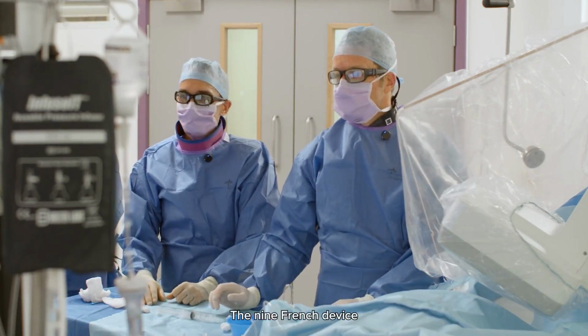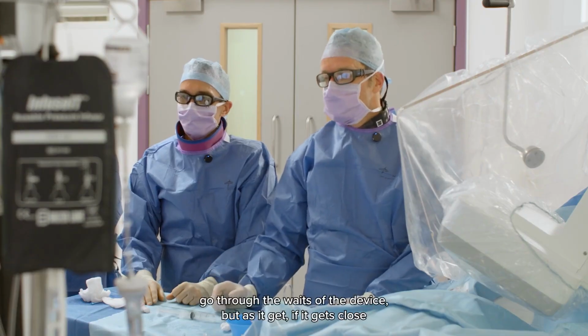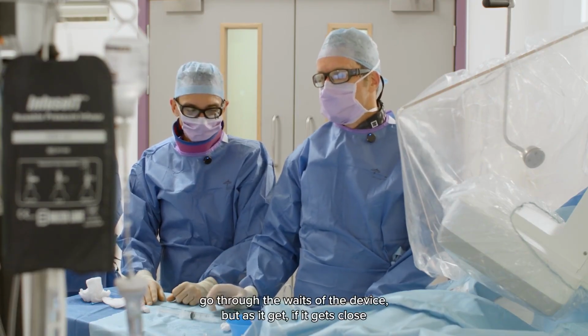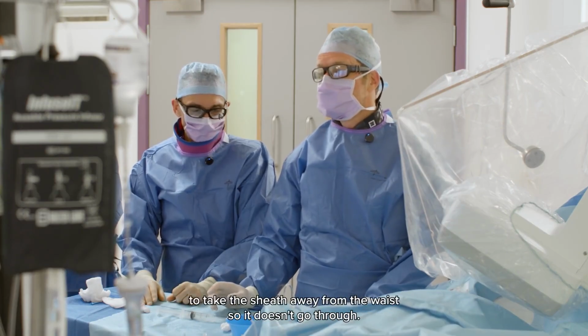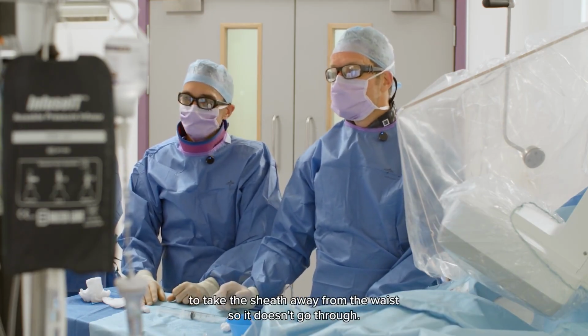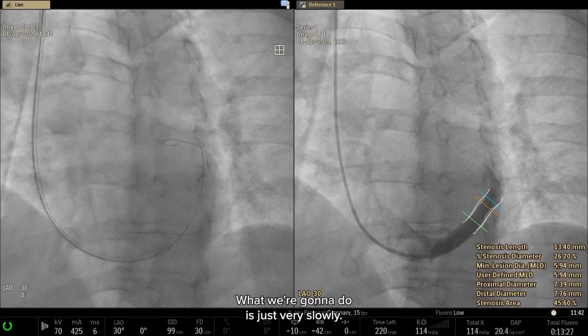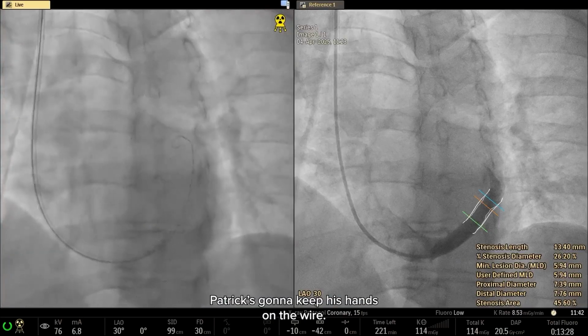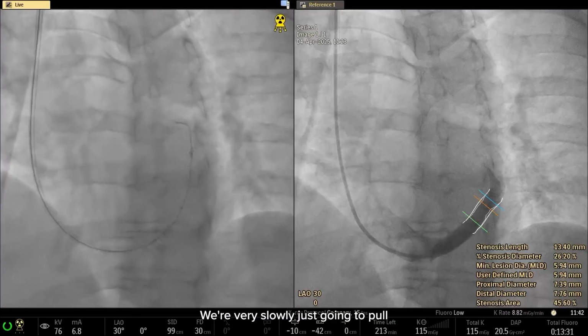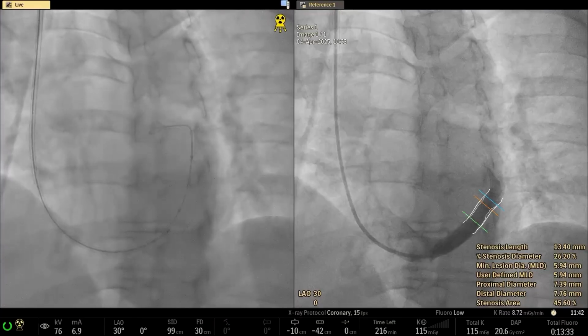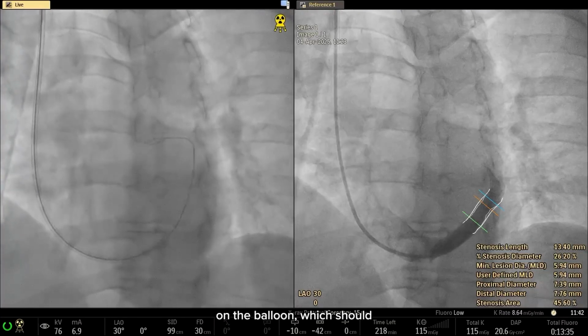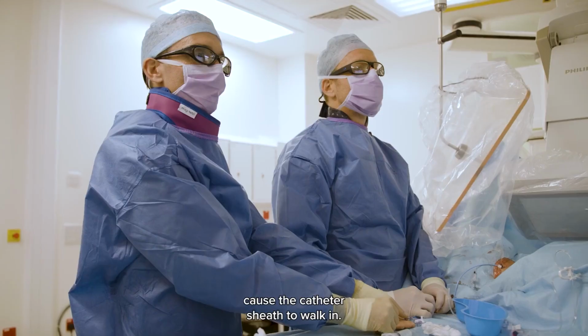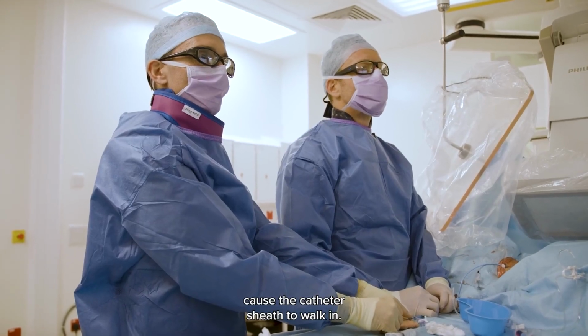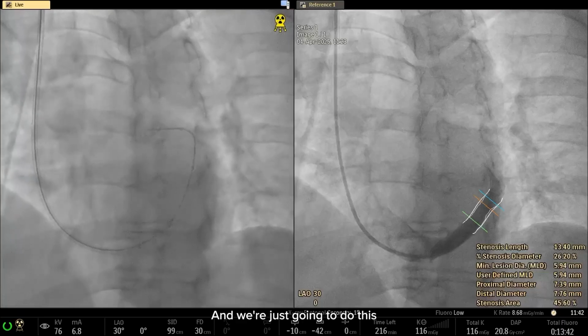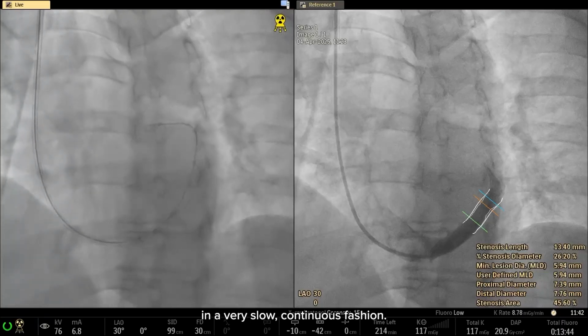The 9 French delivery sheath shouldn't go through the waist of the device, but if it gets close and you're worried, then you push on the wire in order to take the sheath away from the waist so that it doesn't go through. What we're going to do is just very slowly, Patrick's going to keep his hands on the wire, we're very slowly just going to pull on the balloon, which should cause the catheter, the sheath, to walk in. And we're just going to do this in a very slow, continuous fashion.